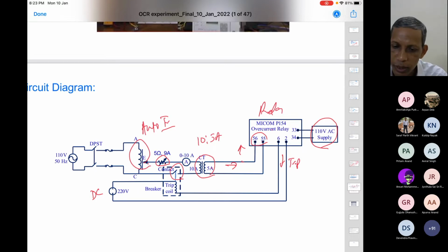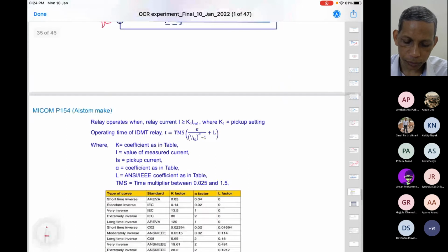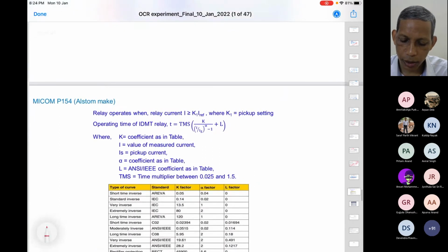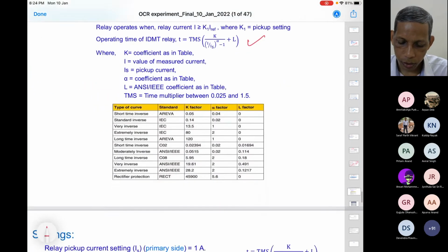We have a pickup setting in the relay. We have selected the TMS, and we have selected a characteristic also, which we'll see. Then you inject current greater than the pickup setting, and note the corresponding trip time. How will we note the trip time? Once the command opens and the relay trips, you record the values, which you can get from the PC.